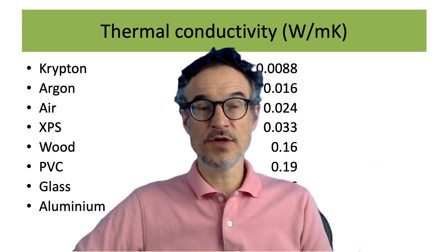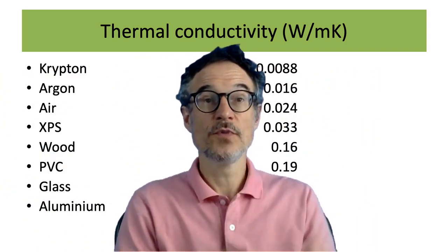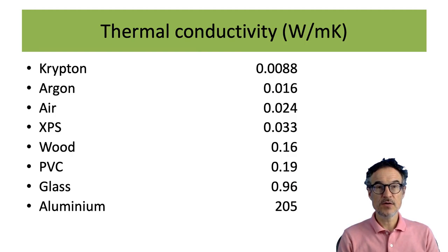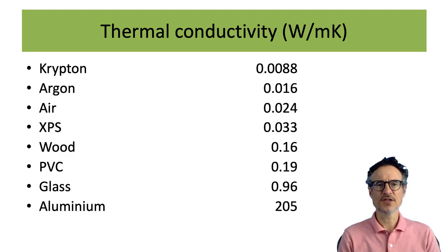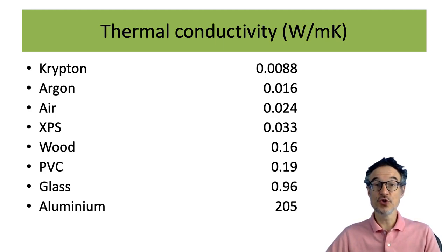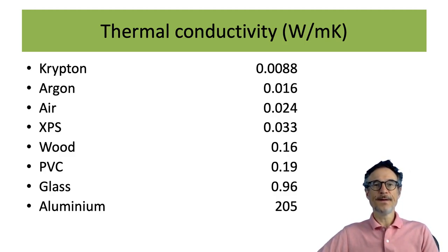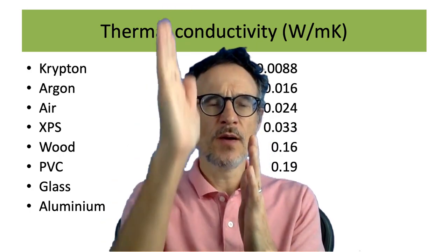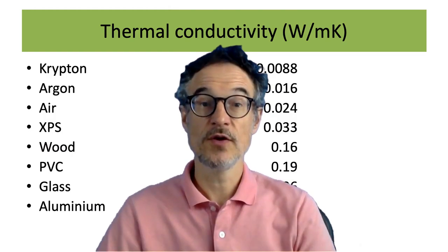At the top you've got the gases, which can go between panes of glass to make double, triple, or even quadruple windows. XPS and other kinds of insulation are available as well — you need something solid with some strength because windows need to hold the glass together. Wood is also good for windows, with a relatively low U-value, making it a good insulator. PVC is also fairly good. You do need glass in the windows, obviously. Aluminium is something you don't want — if the heat's going this way, aluminium going through the window means the heat will just find its way through.